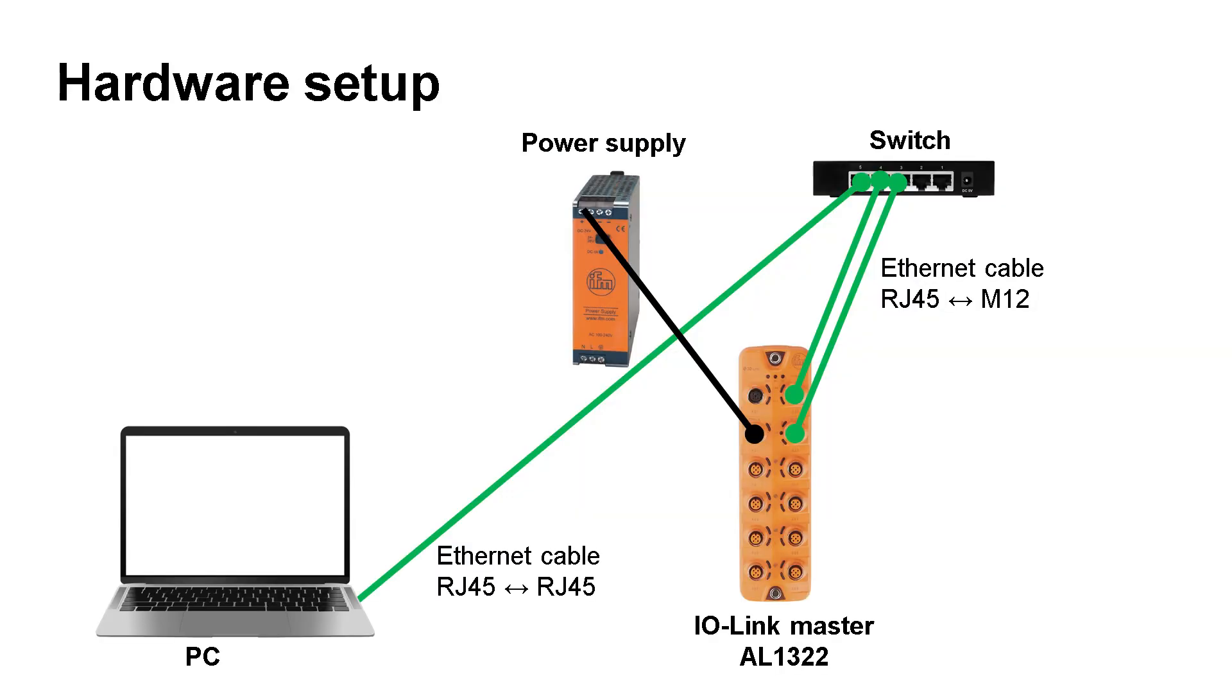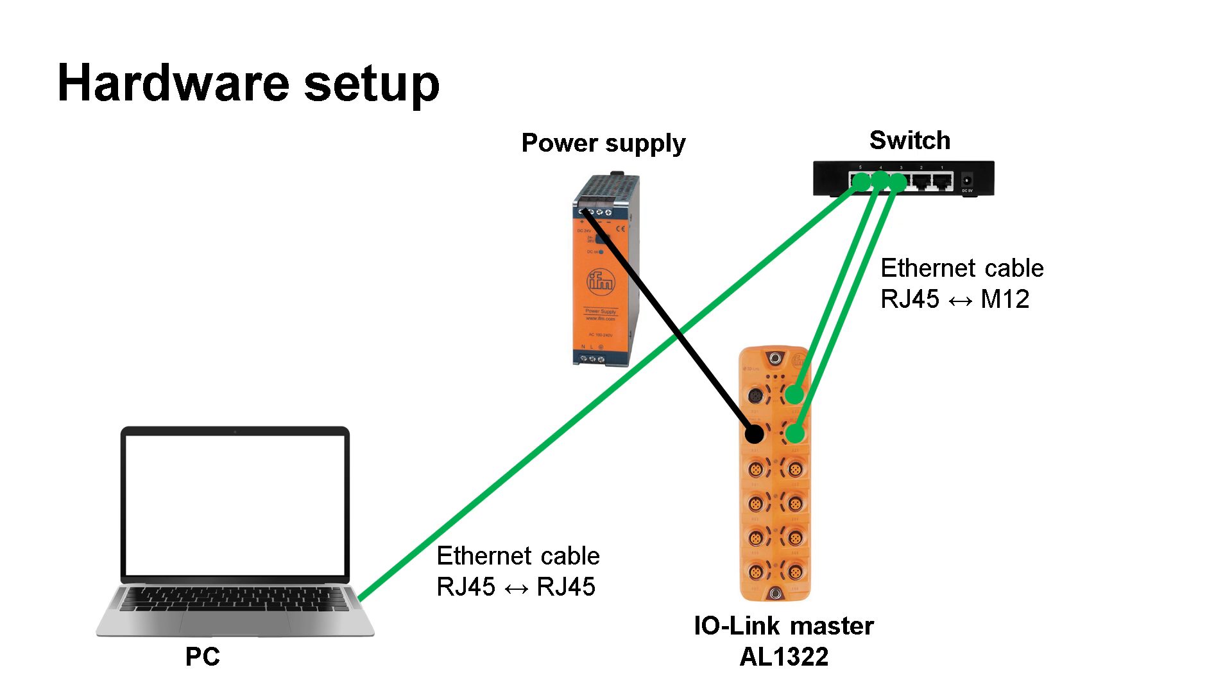In order to work with the controller, please do the following hardware setup as shown. Connect one of the upper Ethernet ports and the IoT port of the IO-Link master to the switch and the switch to the PC via the Ethernet cables. The AL-1322 is a data-line IO-Link master which has two field bus Ethernet IP ports and one extra IoT port. This IoT port can be used for connecting the system with the IT world or for configuring the device. Now we can set the port addresses of the IO-Link master and the address of the Ethernet port of the PC.